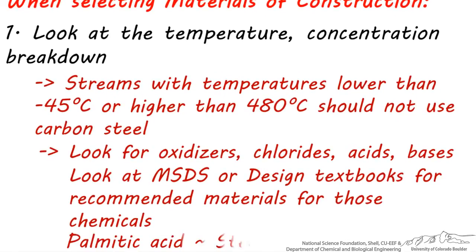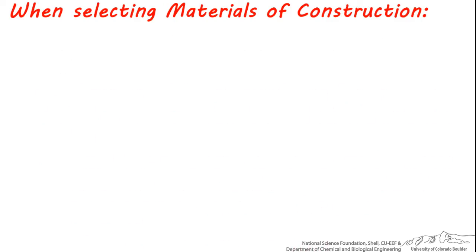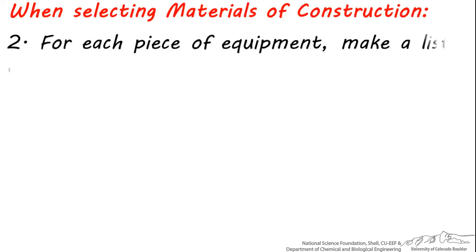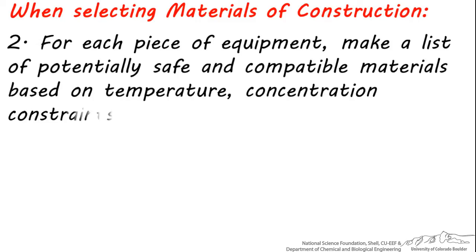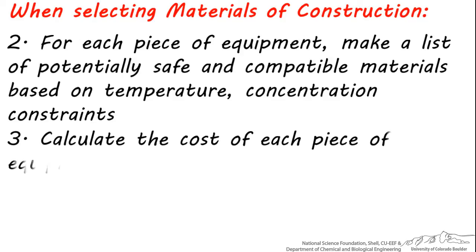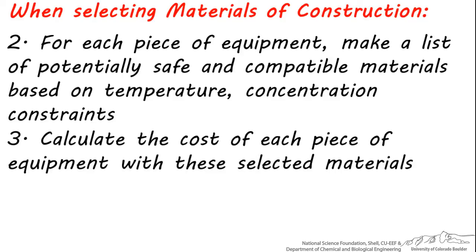For example, if you have palmitic acid as a component in your stream and you can't find it listed in a compatibility chart, find an analogous chemical such as stearic acid. Using this information, you can make a list of potentially safe and compatible materials considering the components in the stream, and then calculate or estimate the cost of that piece of equipment made with those materials to narrow it down to a final selection.